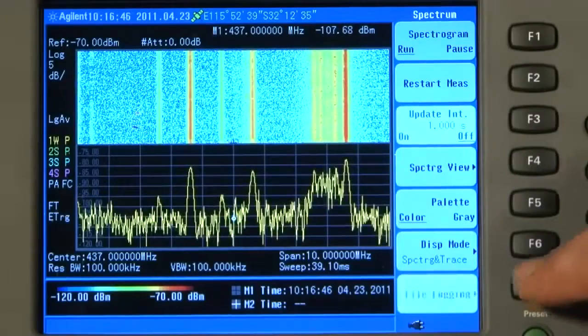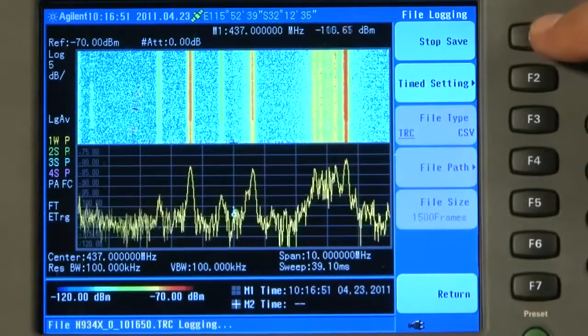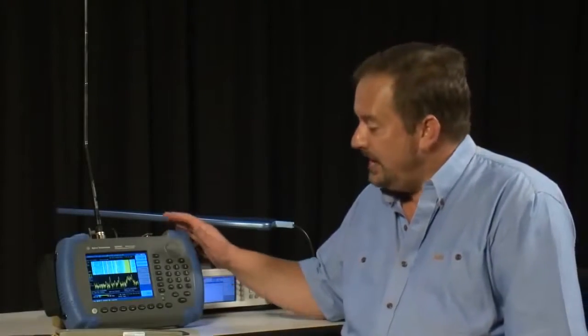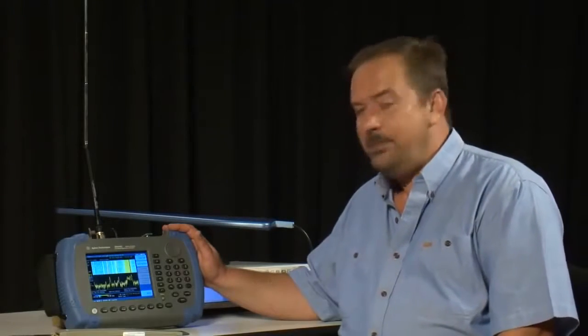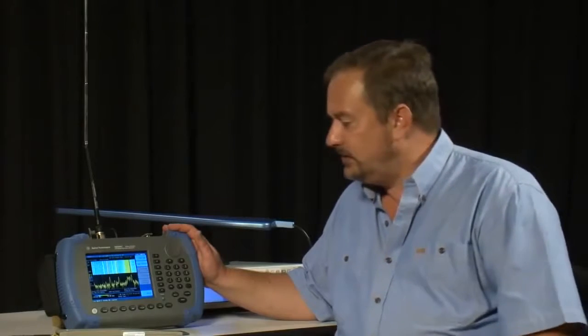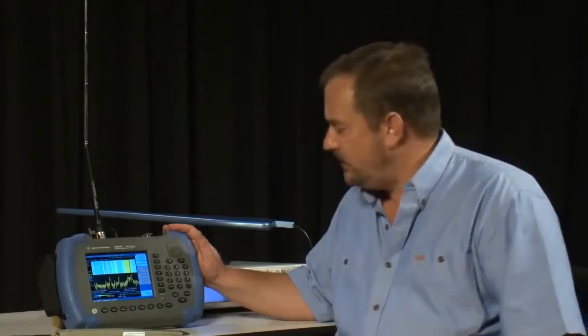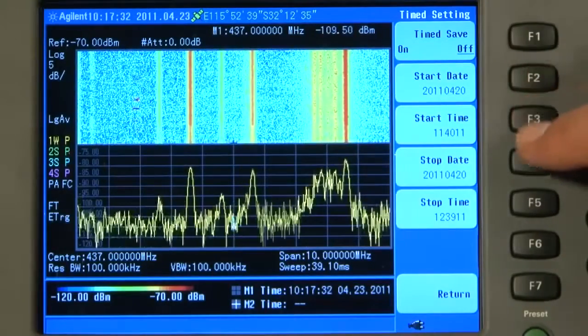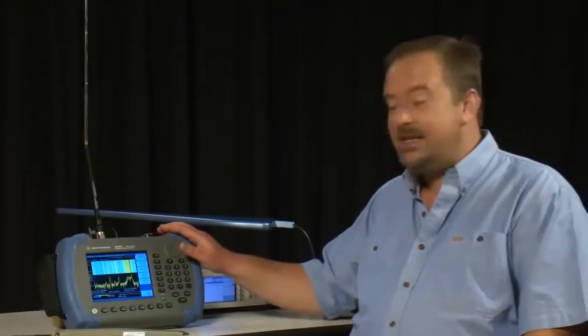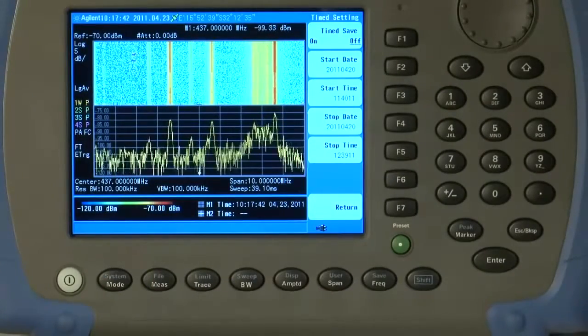Now here is probably the most useful feature of the spectrogram measurement, and that is File Logging. So if I press File Logging and I press Start Save, every trace now is being stored into the internal memory of the analyzer. And we are going to be able to play that back later and analyze what happened while we were away. In fact, for example, if you wanted to set the analyzer up to only record during the night, starting, say, at 10 o'clock at night and finishing at 2 a.m. in the morning, we can set the Time Setting here. Set Time Save On. You can enter the Start Date and Start Time, and Stop Date and Stop Time. And the analyzer will automatically start logging at a predefined time and stop at a predefined time. This is ideal for unattended logging, as it means we can leave the analyzer out on site, return a few days later, and then view what happened during that period.